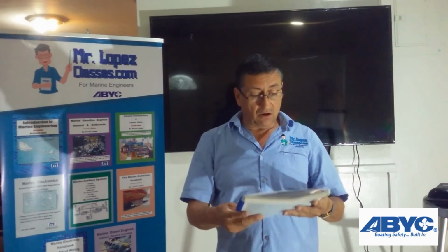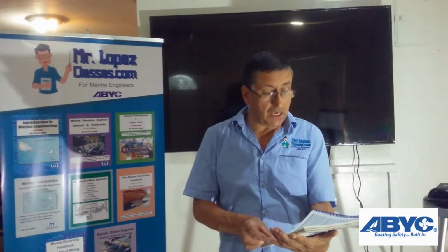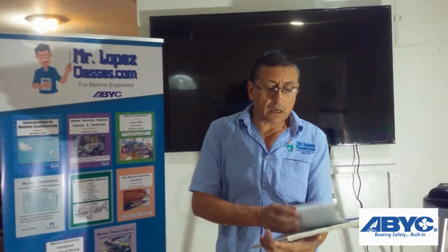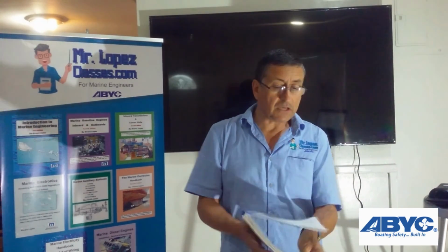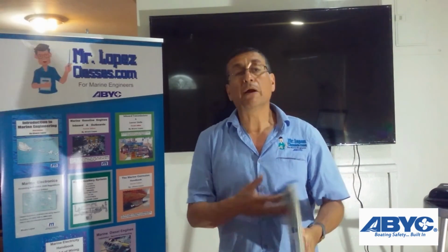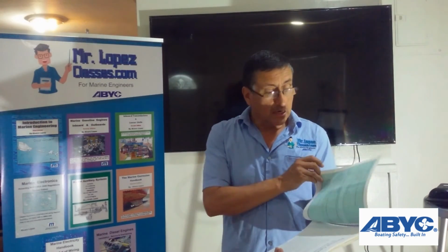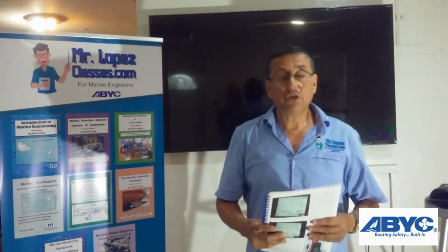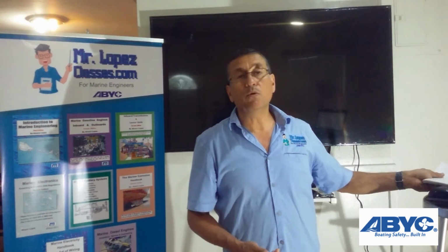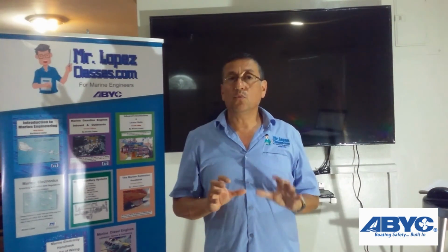The minimum capacity of the battery bank should be 800 CCA, and the electromagnetic interference, I mentioned that. Always use marine inverters. Those are the most important ABYC recommendations in relation to inverters.